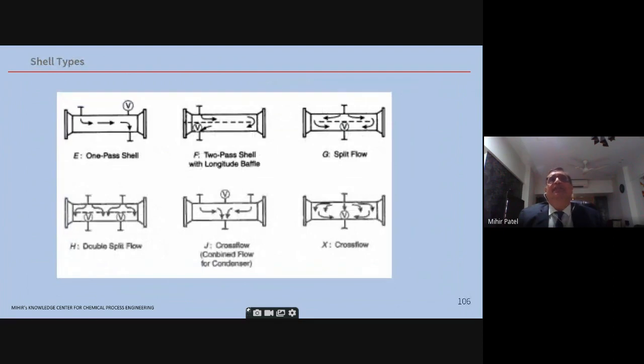Shell types. Now these are the different shell types. The E type is basically the most common configuration without phase change, 1-pass shell. F type is 2-pass shell with longitudinal baffle. Counter current flow is obtained. Baffle leakage problems, however, exist. G type is split flow, so lower pressure drop is obtained. H type is double split flow. Thermosiphon reboilers is the application. J type is divided flow. Flow can enter or exit via the single nozzle. Older reboiler designs have the J type.